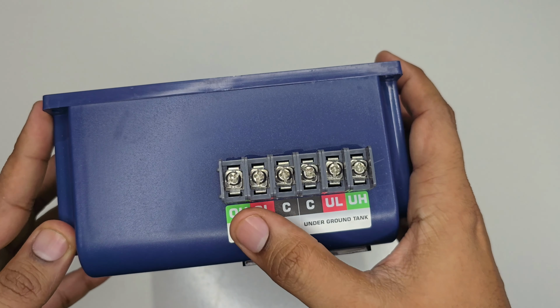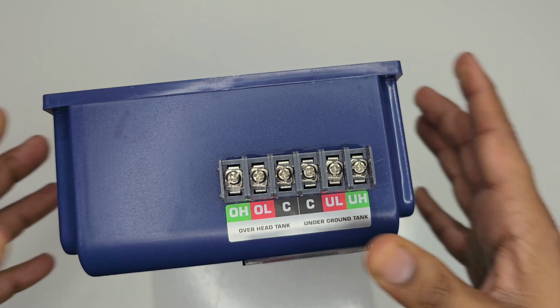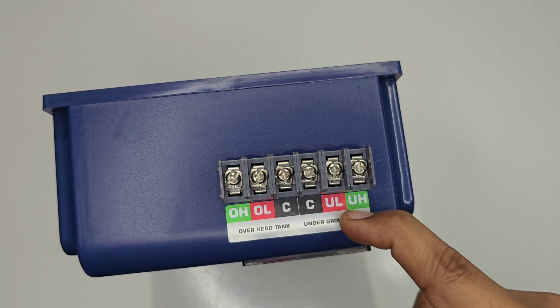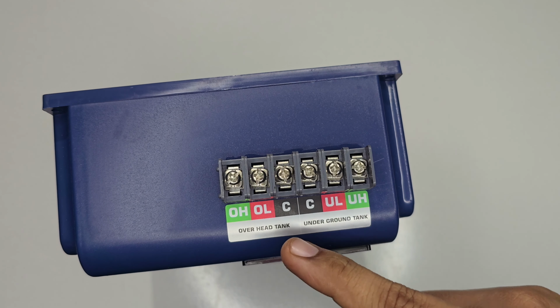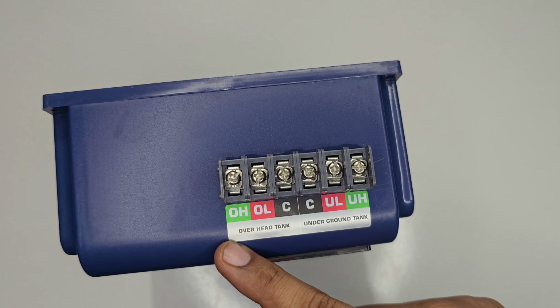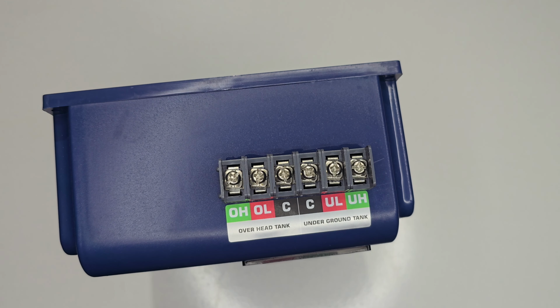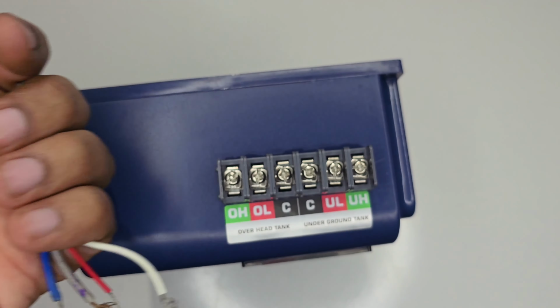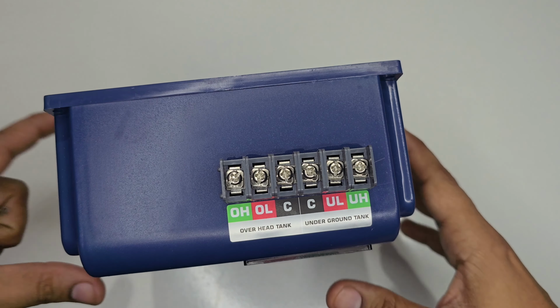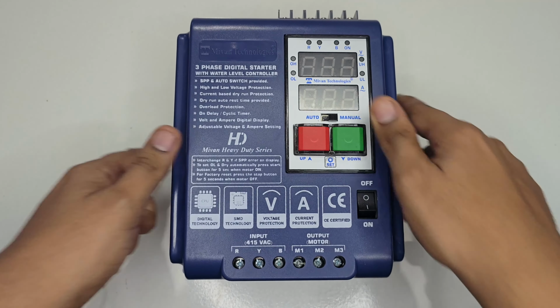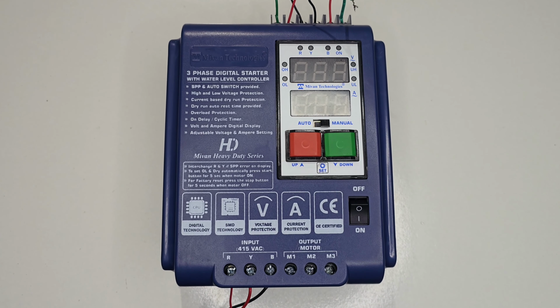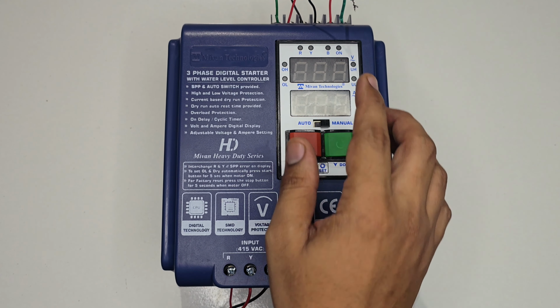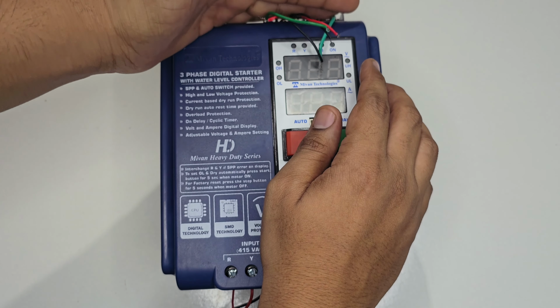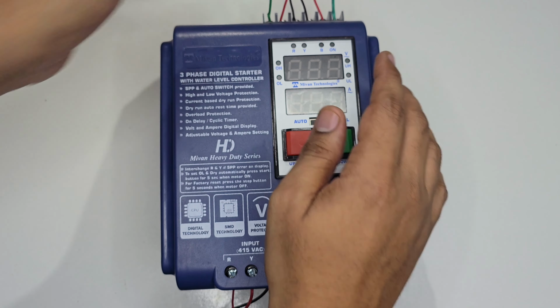These are the sensor connections. Out of it, 3 sensors you need to put in the underground tank and 3 sensors you need to put in the overhead tank. For testing purposes, instead of sensors, I am connecting 6 pieces of small wire at the sensor terminals. Now I have connected the RYB supply at the input terminal and connected 6 pieces of small wire at the sensor connections.